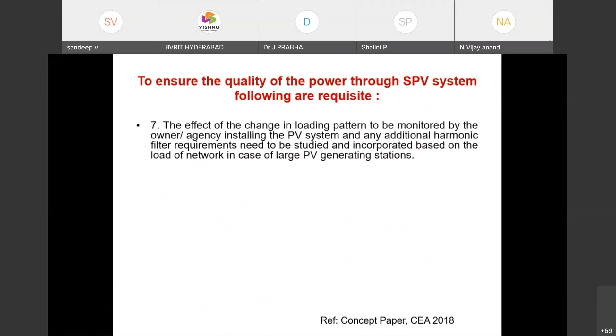Next, they said to effectively handle changes in load pattern, we need some additional harmonic requirements that we need to study. Also, it should be disconnected from the grid when there is any problem or unavailability of grid supply - isolation should be taken care of as per the guidelines.